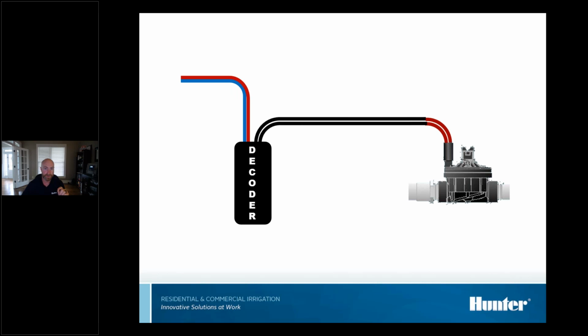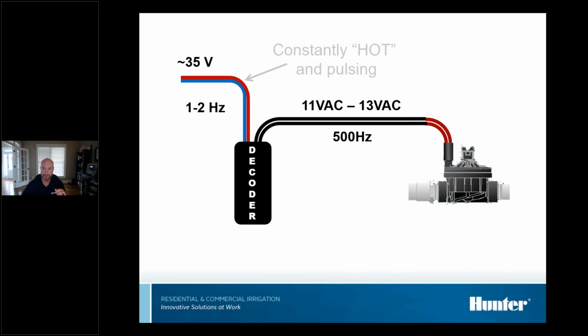This is opposed to the decoder system. So you've got your 2-wire over here on the left side. Like I talked about, it's pulsing at roughly 35 volts, 1 to 2 hertz. And then the signal that actually goes from the decoder to the valve solenoid is a little bit lower, but it's turning faster, so it's almost like we're tricking the solenoid into coming on. It's actually buzzing at 500 hertz.